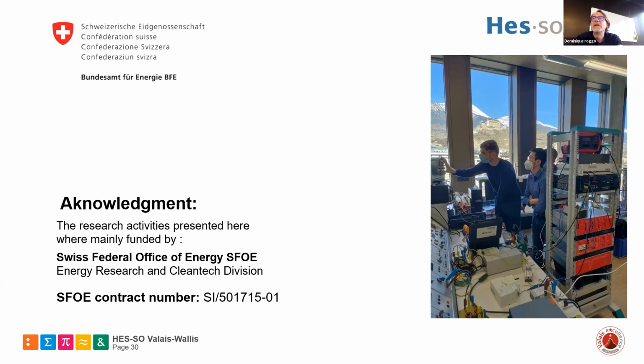Yeah. We did not come so far with this test setup with two devices, data concentrator and smart meter. We had previously made tests in the ZNet project at Tecnalia in Spain, together with our colleagues from Basque University in Bilbao, and there we had 40 smart meters altogether and much longer lines. It was the real first prototype from Schaffner, and already there we could notice a slight improvement in the situation with 30 to 40 smart meters. Of course, we should go back, and that's not our job. Schaffner should go back to Tecnalia, where we have this very nice test site with many smart meters.